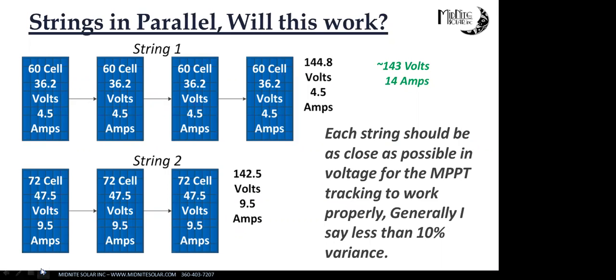VOC. So the rule of thumb here is if the modules are going in series with each other, the current needs to be within about 10% of each other. If the strings are going in parallel with each other, the voltage of the string needs to be within about 10% of each other. So that's just something to keep in the back of your mind when you're looking at these solar salads, and when you're looking at modules.